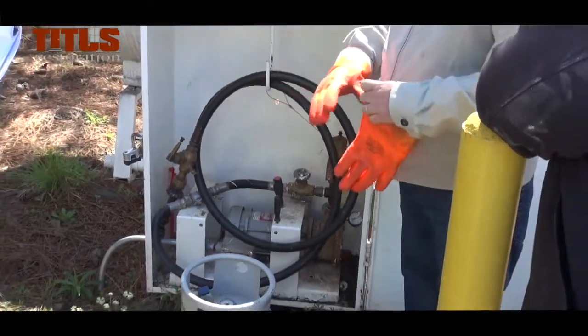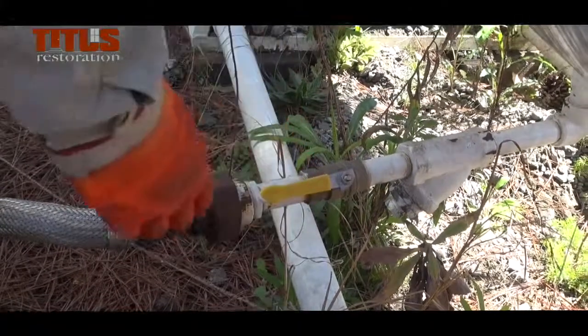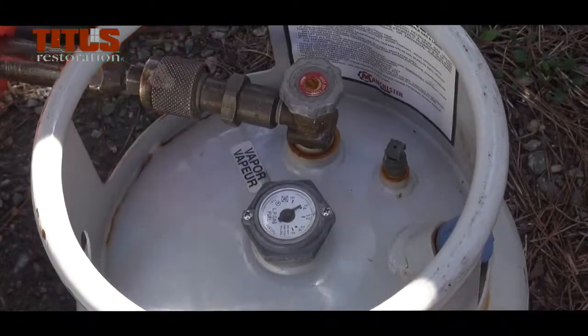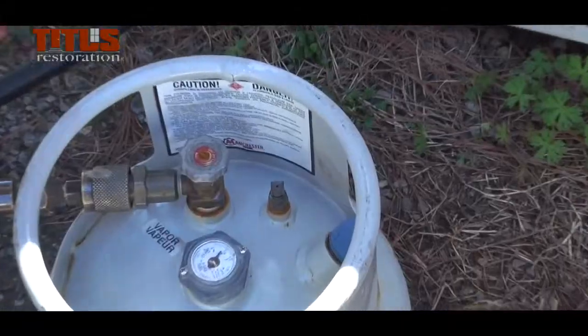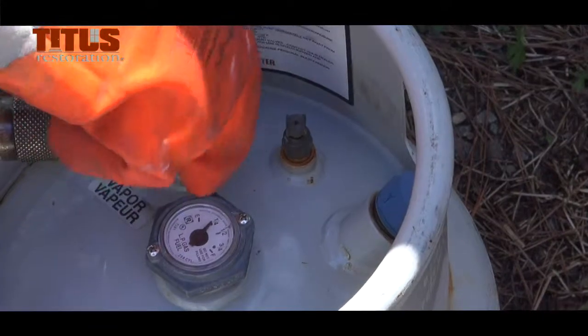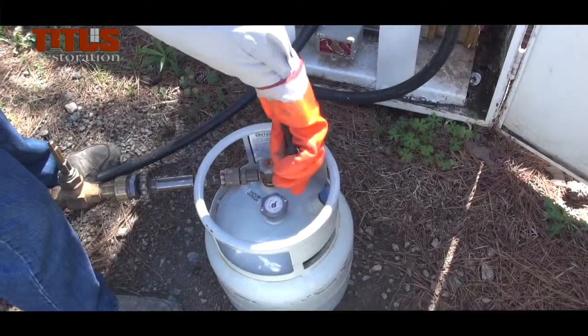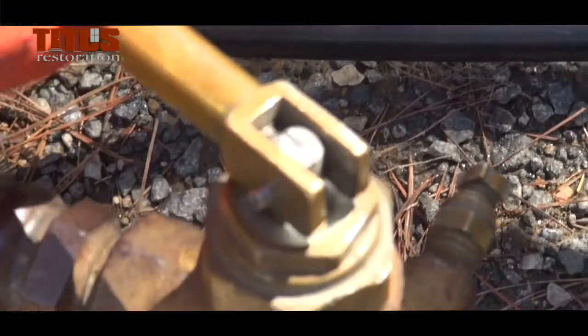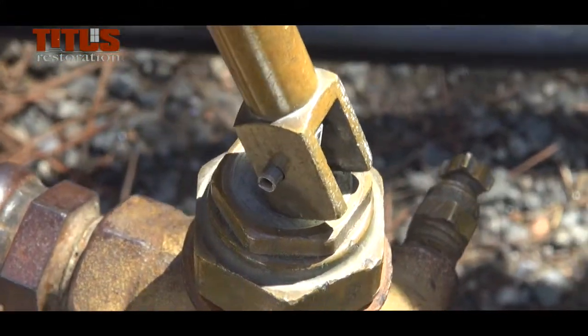To fill the tanks, the following is required. While wearing protective gloves and goggles, turn on the transfer pump. Connect the hose coupling and nozzle from the tank to the cylinder at the main fill valve. Open the main liquid valve no more than two turns. Open the bleeder valve one quarter turn. Turn on the transfer pump by pulling the black plastic pin and pulling up on it to the perpendicular position.